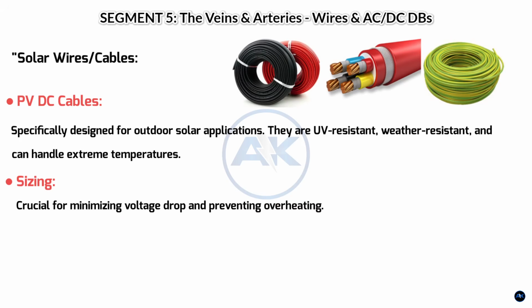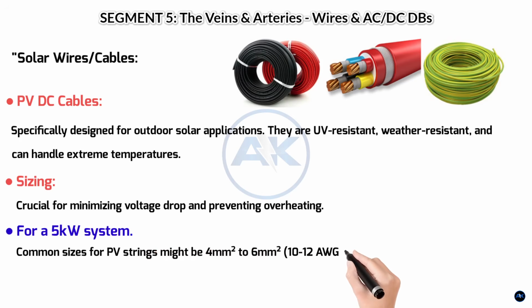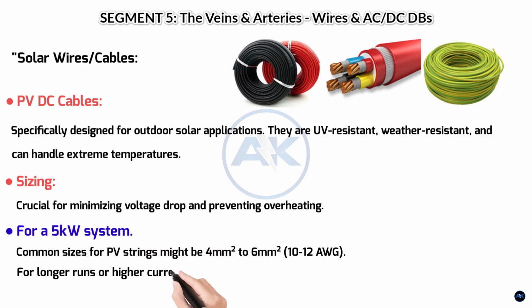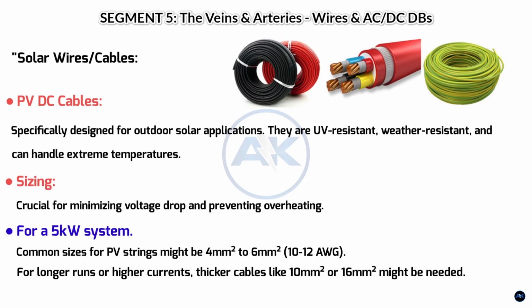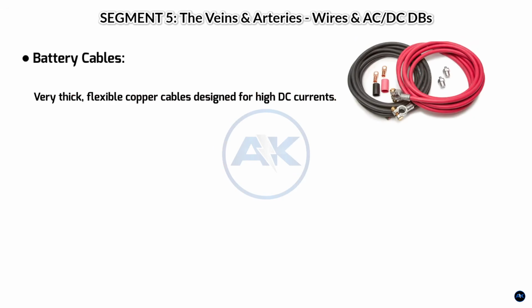Sizing is crucial for minimizing voltage drop and preventing overheating. Use online calculators or consult your electrician. For a 5 kilowatt system, common sizes for PV strings might be 4 mm squared to 6 mm squared, 10 to 12 American wire gauge. For longer runs or higher currents, thicker cables like 10 mm squared or 16 mm squared might be needed. The general rule is to aim for a voltage drop of no more than 2% of the system's voltage. Color coding: red for positive plus, black for negative minus. Battery cables: very thick flexible copper cables designed for high DC currents.